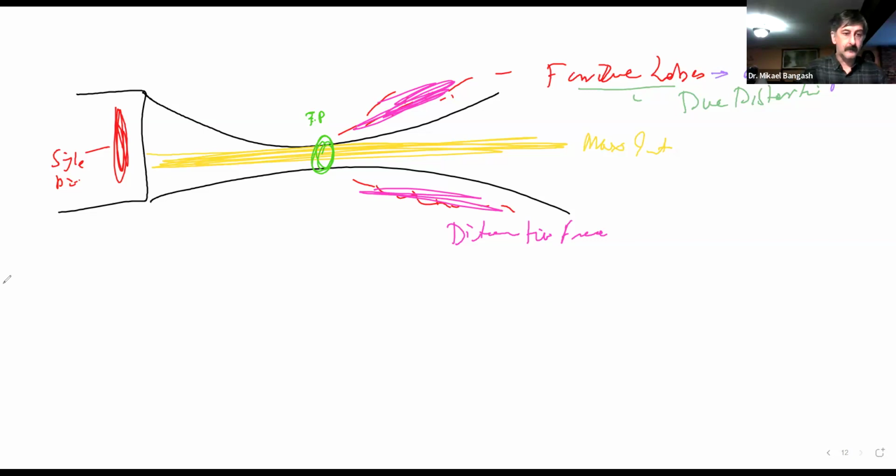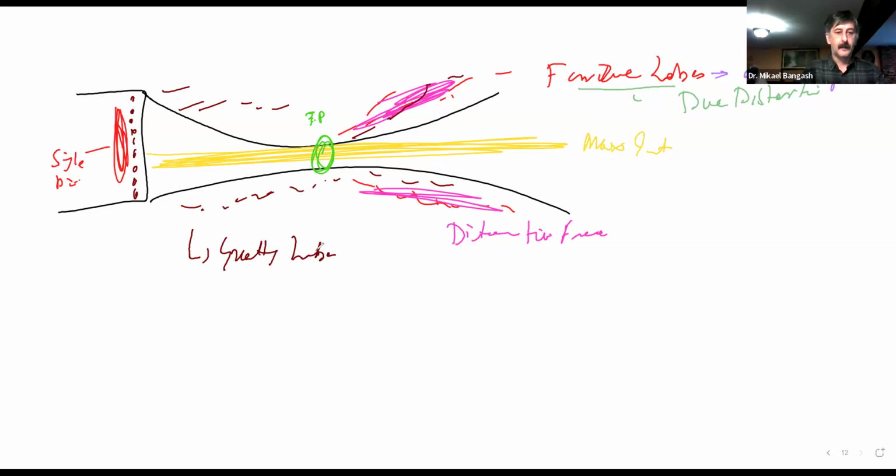But likewise, for your array or phased transducers, which means we have multiple PZTs, what would they have? We will have grating lobes. And where did we find grating lobes?